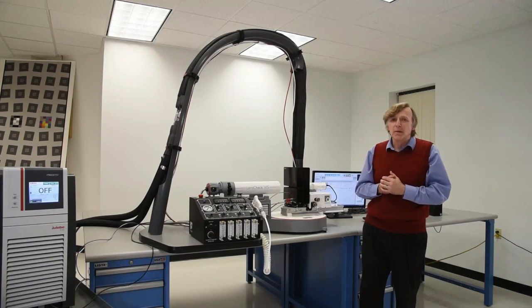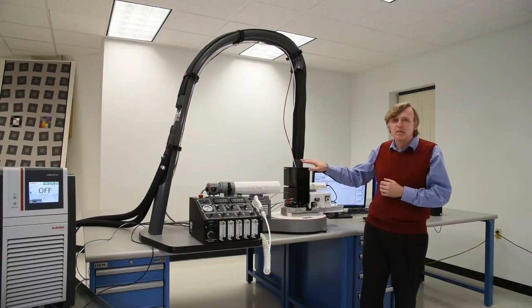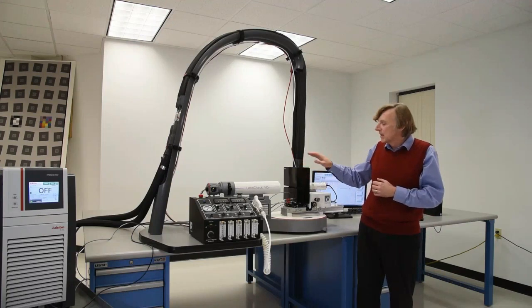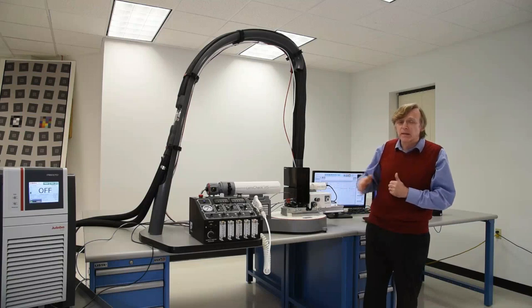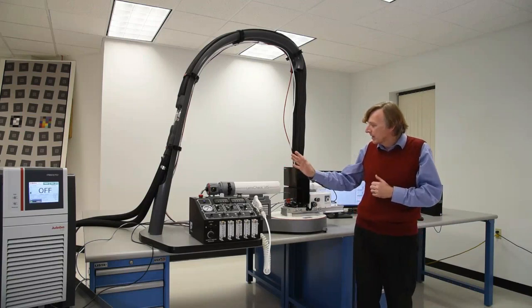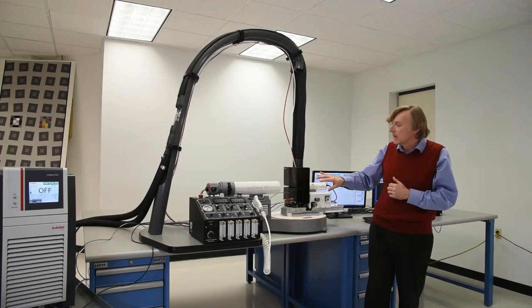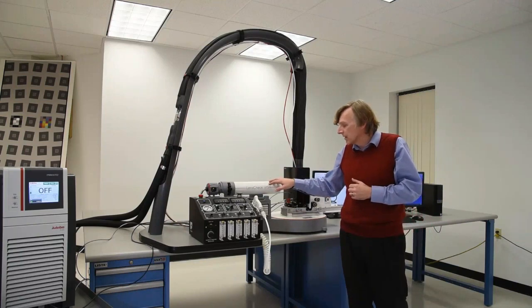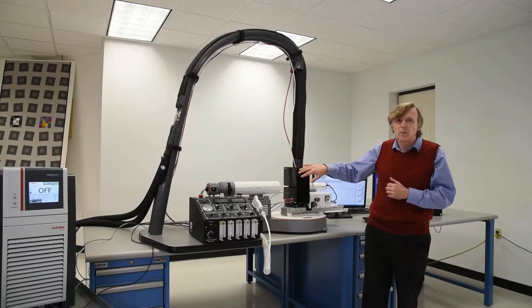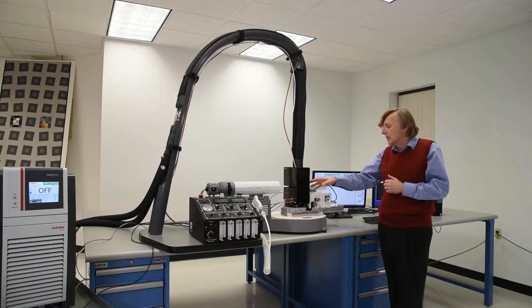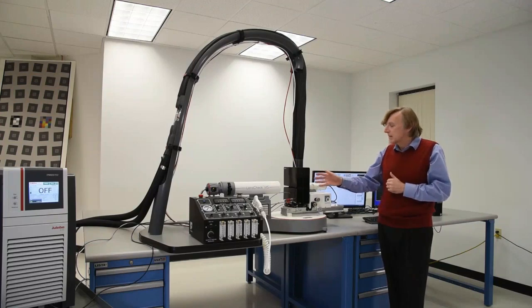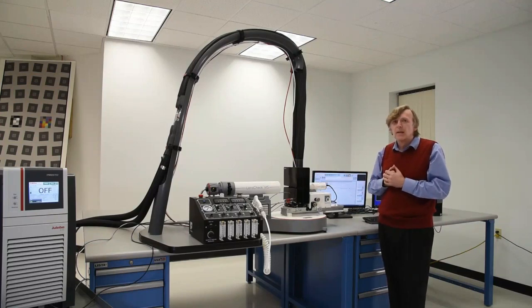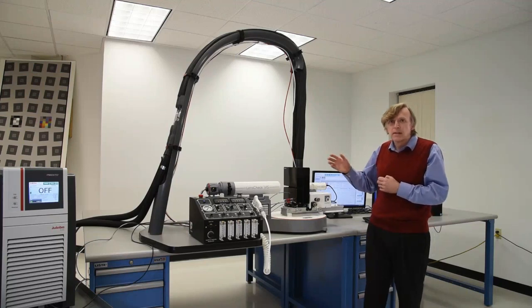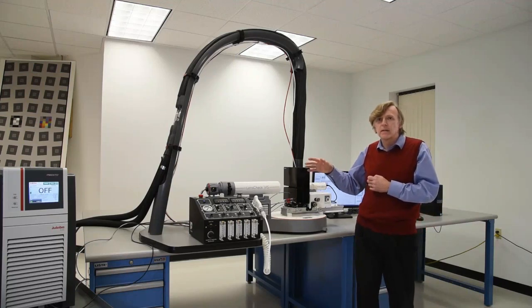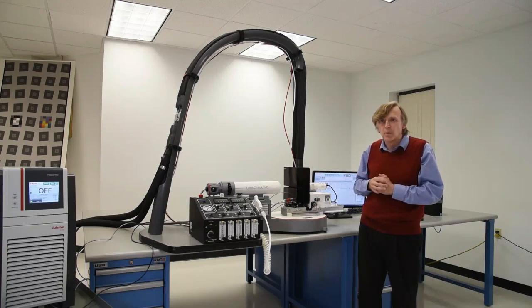It is generally a rule with any metrology equipment that the apparatus itself cannot affect the measurement being made. In the case of lens measurement equipment, this means that we cannot introduce something into the optical path that will affect the performance of the lens under test. On the input side, where the light is collimated, we can and do place high-quality flat windows, but this is not true at the sharp end where the image forms, because doing so would introduce spherical aberration. So we cannot seal the image side of the chamber. An obvious consequence of this restriction is that condensation will form on the lens under test as soon as the temperature drops below the ambient dew point.